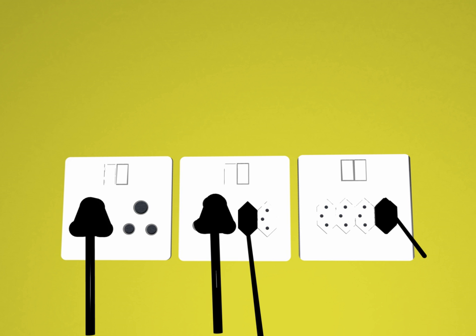The two types of plug systems also differ in that IEC 60906-1 plugs, both 2-pin ungrounded and 3-pin grounded, always have been defined to have partially sleeved line and neutral pins, while the Swiss type 11 and type 12 plugs formerly were allowed to be without partially sleeved pins. However, since 1 January 2013, only type 11 and 12 plugs with partially sleeved line and neutral pins are allowed to be imported and distributed in Switzerland to reduce the risk of electrical shocks.